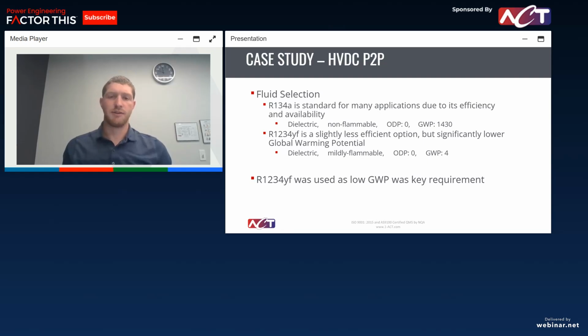So first, selecting fluids. In this case, the customer needed a low global warming potential fluid, so we ended up choosing R1234yf. So it's significantly lower global warming potential. It's not quite as efficient as R134a, which we often use, and it does have mild flammability, but that was based on the requirements in the application. We had to choose that fluid.